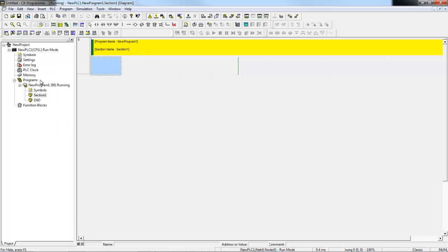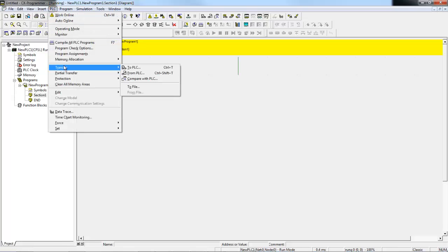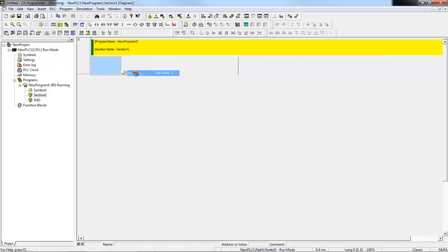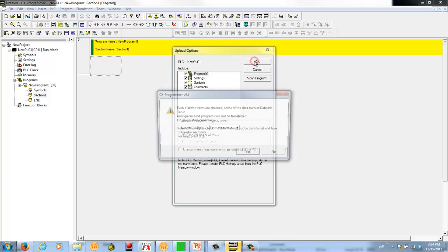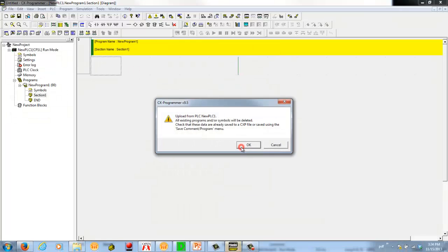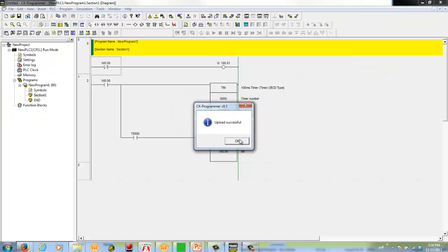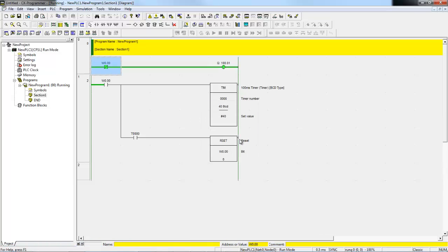So since I manually created my project, I did not get the program from the PLC. So the next thing I'd like to do is actually transfer from. Let me show you how to do a transfer. So under the PLC menu, about halfway down is transfer. We have to, from, and compare. In this case, I created a blank project, so I'm going to select from PLC. It uploads the code, and there's my program there. So now I've seen how to connect. We've seen how to transfer the program.